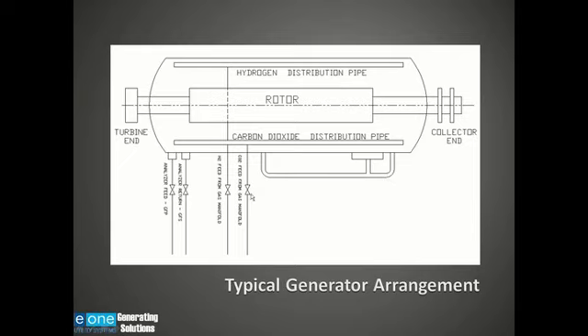So what I do is I bring carbon dioxide into this bottom header. Carbon dioxide being heavier than air will create a blanket and flow up, and the air being lighter than carbon dioxide will come out of this top header. Once I'm satisfied that I've got all of the air out of the case, and I've got the case filled with CO2, now I want to put hydrogen in there. So what I'm going to do now is open this line to hydrogen, hydrogen being a lighter gas than CO2, open this line to vent, and the hydrogen pressure will force the heavier CO2 gas out this line. So that's a very simplistic description of how a generator is purged.